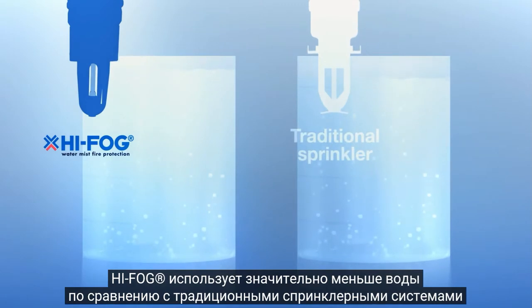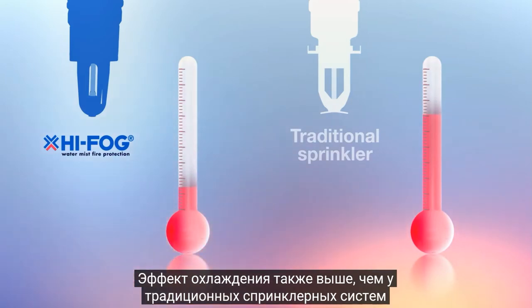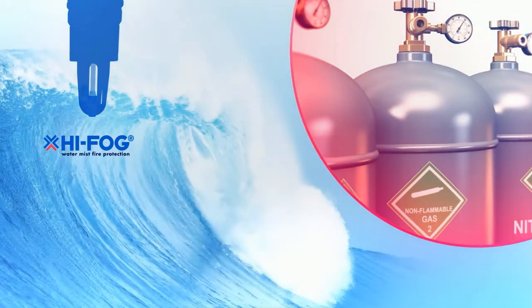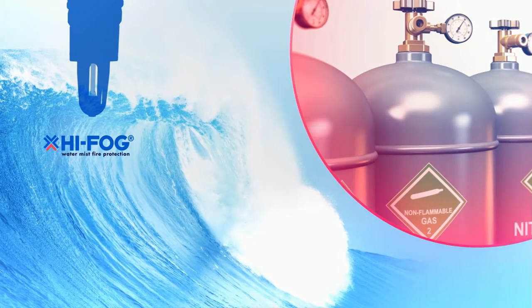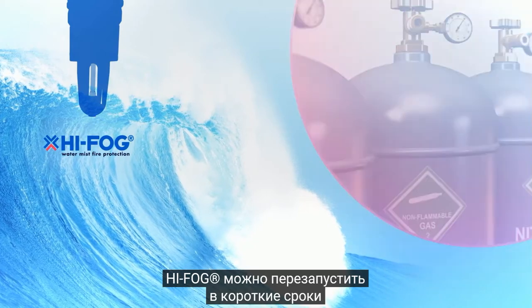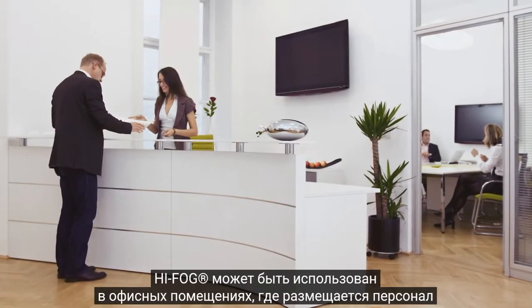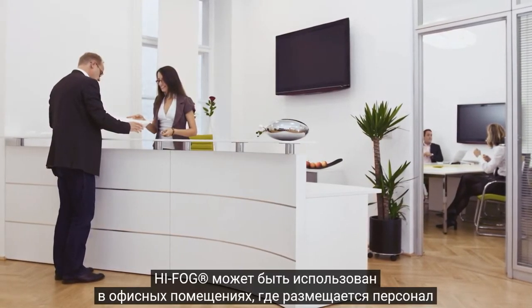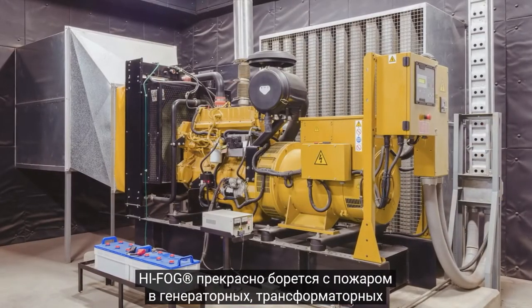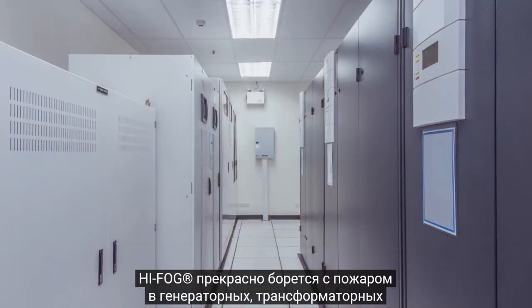HI-FOG uses significantly less water compared to traditional sprinkler systems. Cooling is also more efficient in comparison to traditional sprinklers or low-pressure water mist systems. Unlike expensive gases, water is a commodity with no risk of being banned by authorities. Using water mist is not restricted to one shot of operation either. HI-FOG provides total protection for all spaces of a data center. Water mist fire protection can also be used in office areas where personnel are located, and it offers an excellent choice in fighting fire in technical areas with backup generators, transformers, and UPSs.